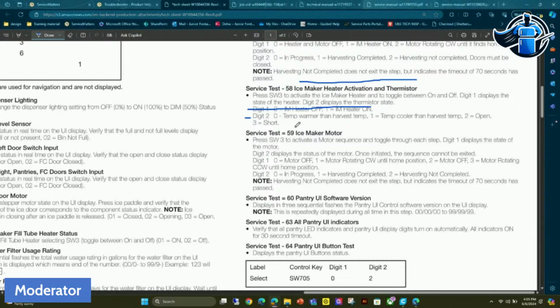If you're seeing a 0, the temperature is too warm and the unit won't harvest. You always want to see an 01 when you're in test 58, letting you know the temperature is cooler than a harvest temp. If I show up to a customer's home and the ice maker isn't working, and I check test 58 and see double zeros, that's telling me I'm having a temperature issue in the ice maker compartment.